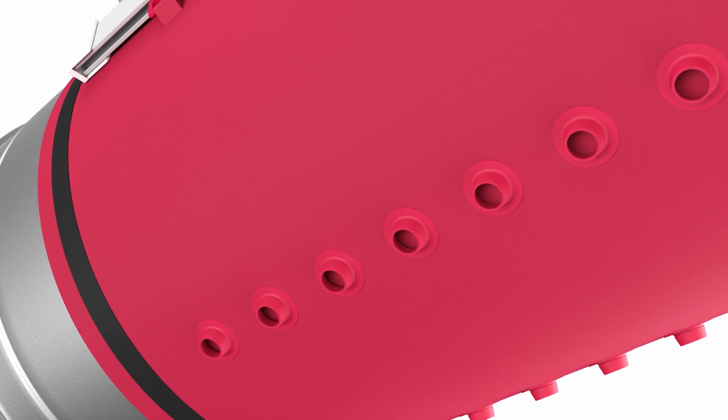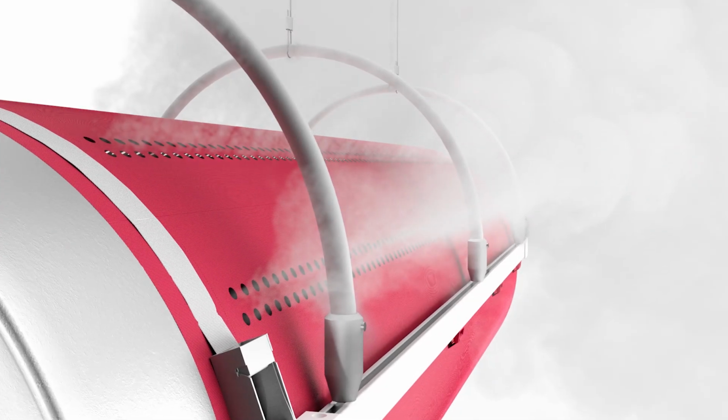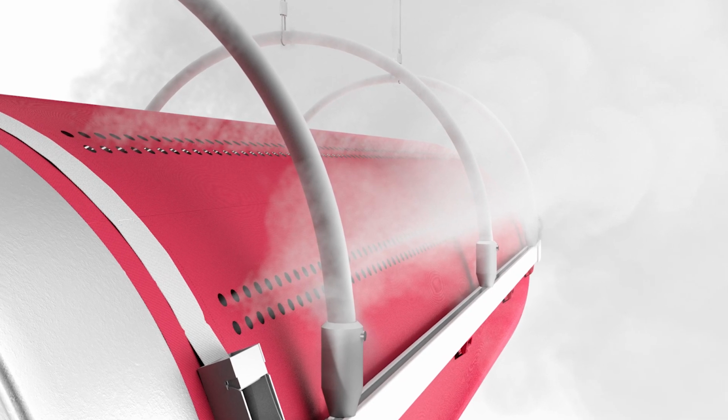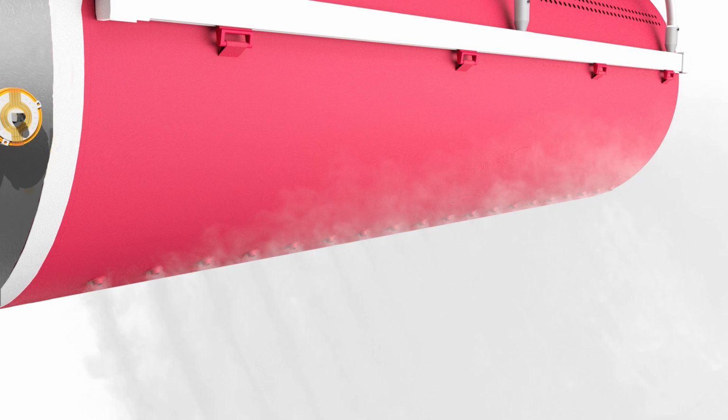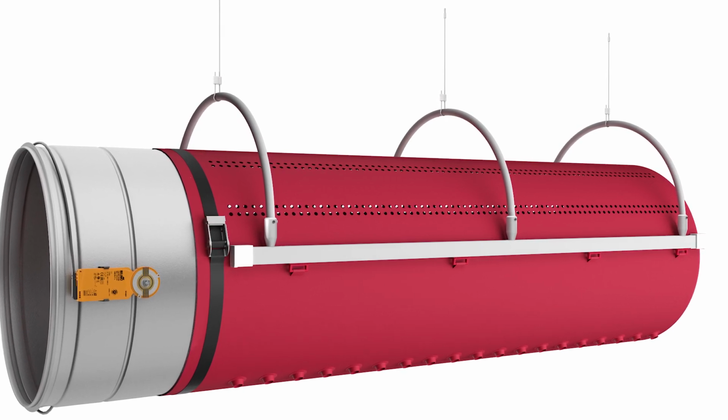It has larger perforations, nozzles or jets, which accelerates the airflow, thus allowing the heated air to reach the occupied zone, despite heated air's natural tendency toward rising. The upper and lower sections can even be designed with their own unique static pressure and air volume to meet the specific requirements and comfort levels of the application. With the Fabric Air VarioDuct, there is no need to compromise between cooling and heating conditions. It's two solutions in one duct.